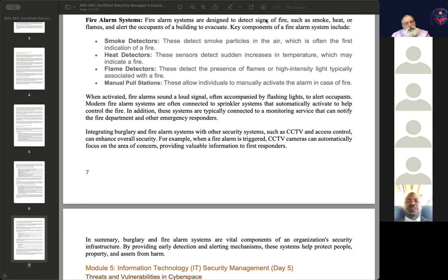The ionization, because how many times you say, I smell fire, I smell something is burning, but there is no smoke around you. Okay? This is the job of the smoke detector that makes ionization. You understand? Checks how many positive ions are in the environment, in the area that works. This one will give you alarm on time. Okay? But can give you a false alarm also if you have lots of dust.